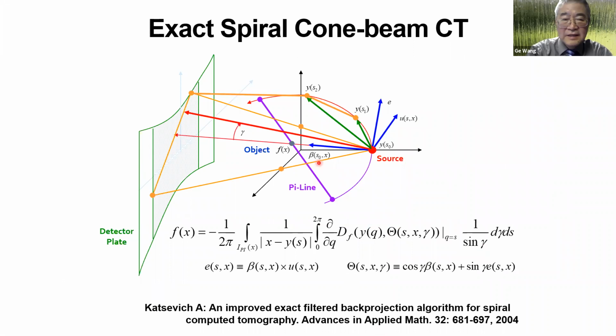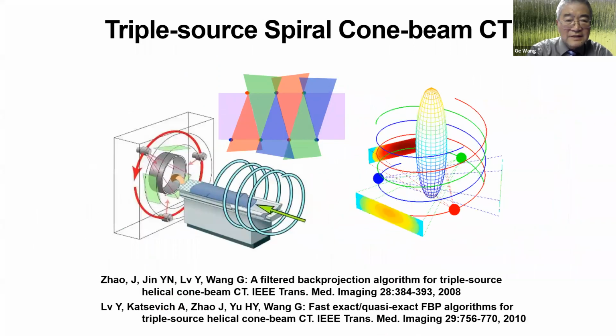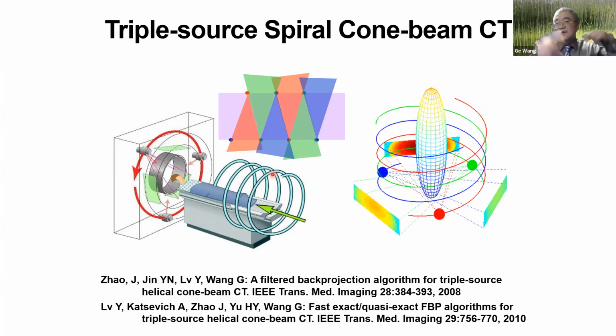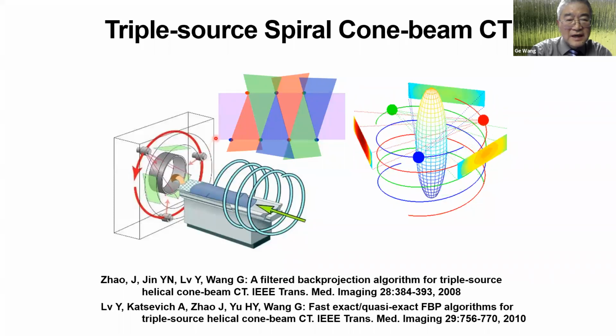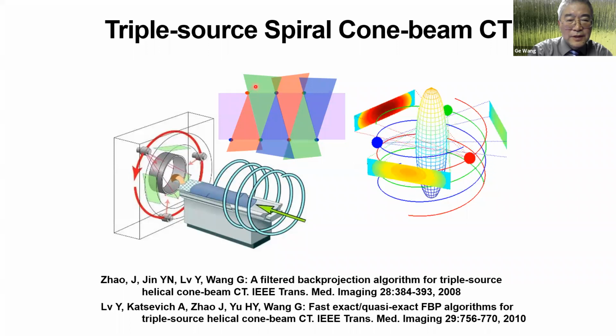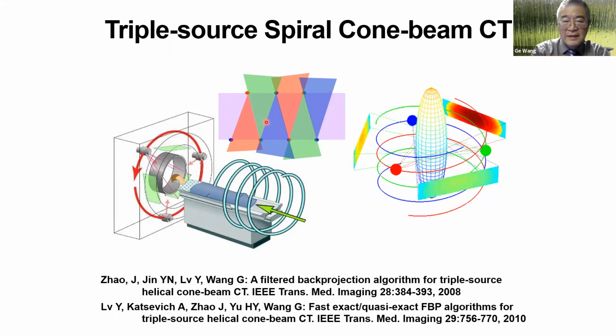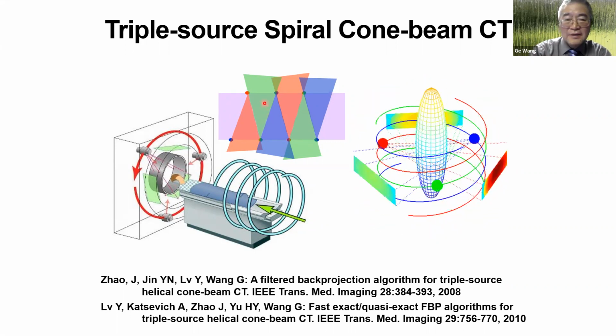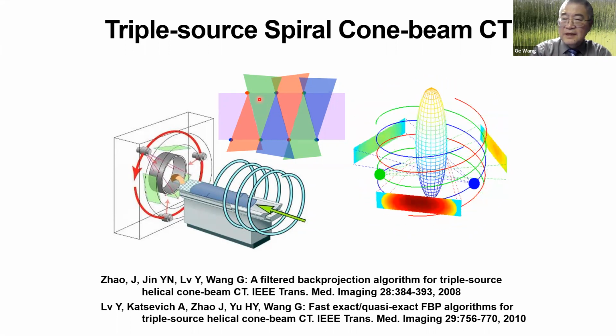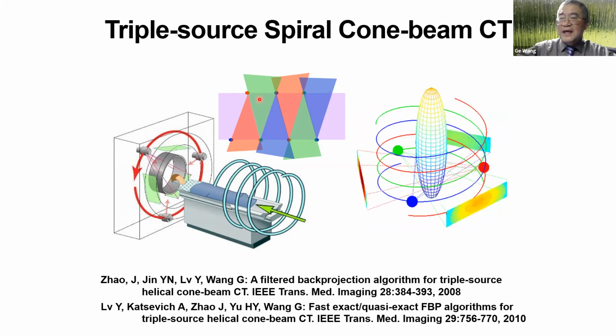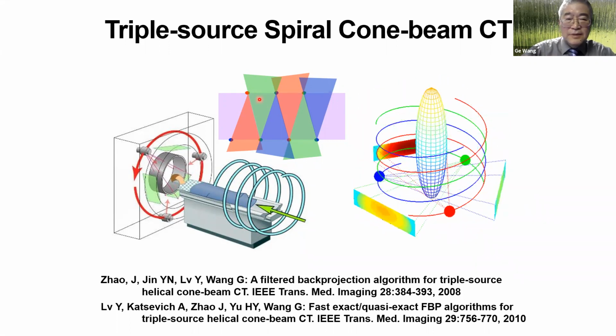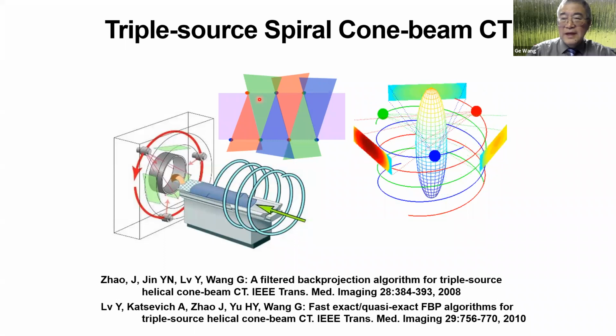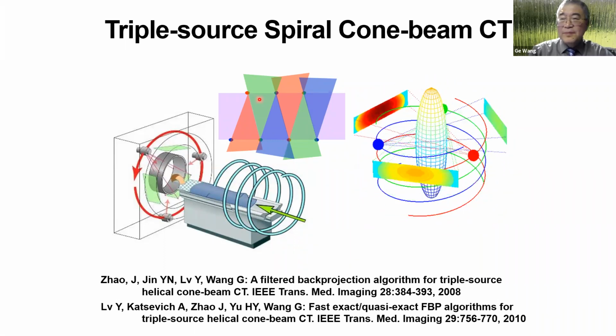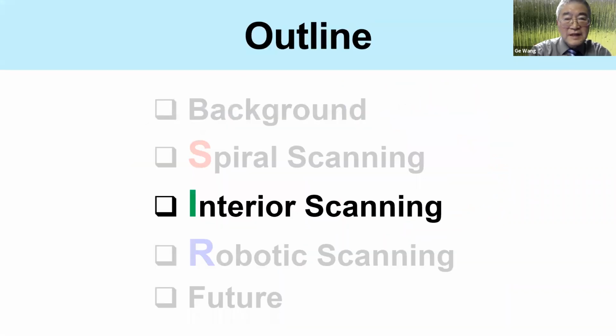It took the field over a decade to derive a theoretically exact cone beam reconstruction algorithm. This is also known as the Katsevich algorithm. In collaboration with Katsevich and others, we extended the work and considered triple source scanning. With this triple source scanning geometry, you get a red cone, a green cone, and a blue cone, and you still have this nice mosaic pattern to perform very efficient, theoretically accurate cone beam reconstruction. So the evolution from fan beam to cone beam is to collect more data so you can improve temporal resolution. The triple source spiral CT geometry really made a step forward by collecting the cone beam data in parallel. So this is the first topic I want to cover.